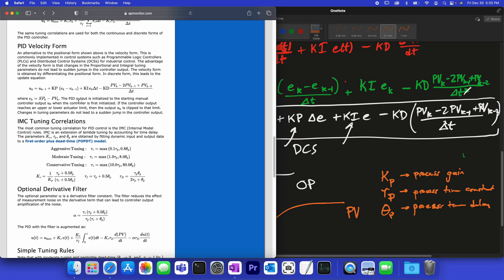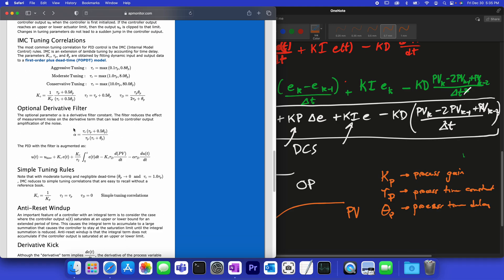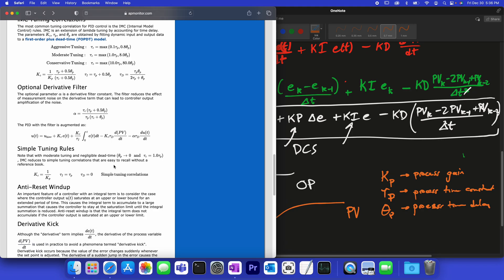Using those correlations, you come up with kc, tau_i, and tau_d — or equivalently kp, ki, and kd — and then implement and test them. There is also an optional derivative filter. For simple tuning rules when you have negligible dead time, just use a controller gain equal to the inverse of the process gain, and an integral time constant equal to the process time constant.